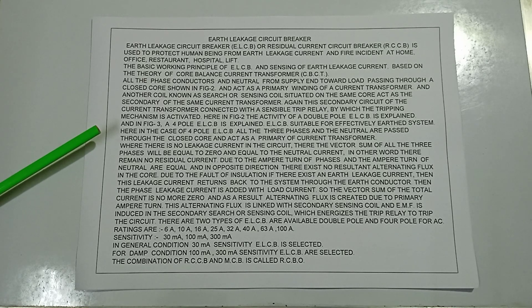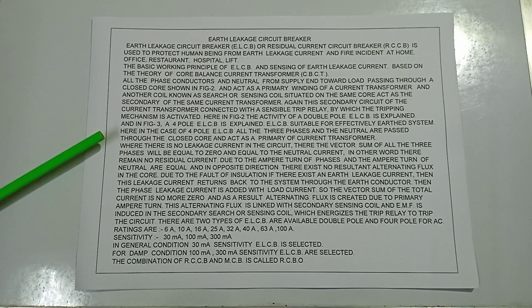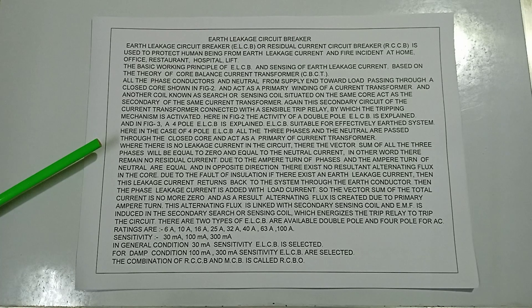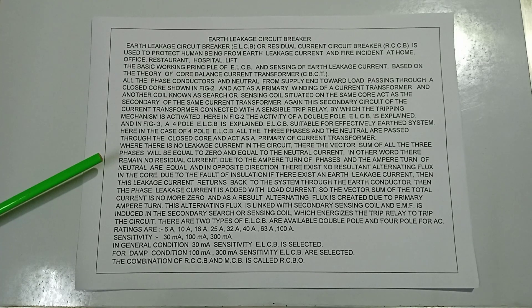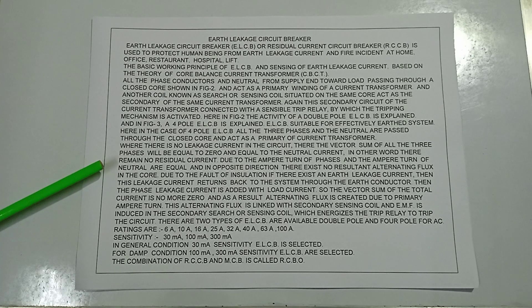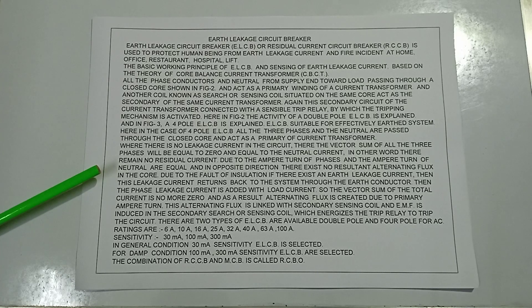ELCB is suitable for effectively earthed systems. In the case of a four-pole ELCB, all three phases and the neutral pass through the closed core and act as the primary of the current transformer. The ampere-turns of the phases and neutral are equal and opposite, so there is no resultant alternating flux in the core under normal conditions.